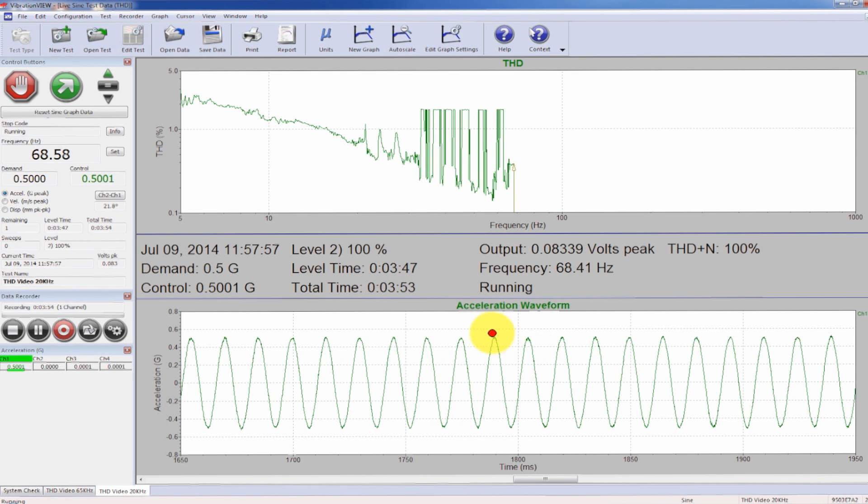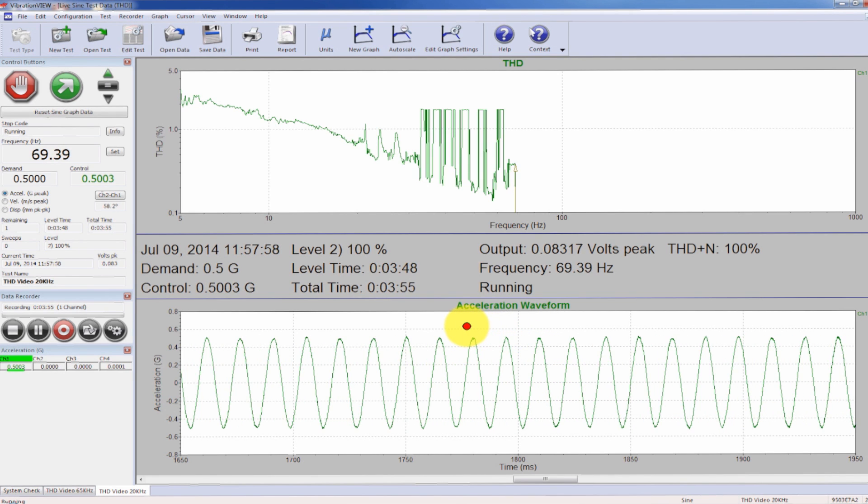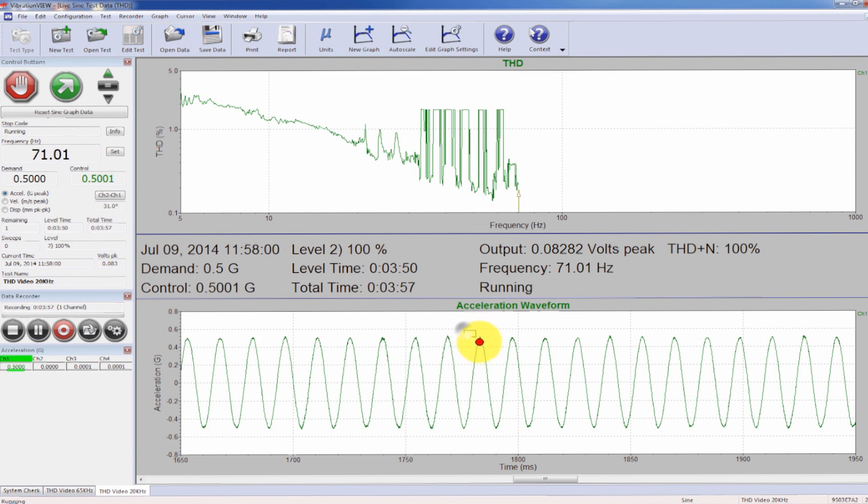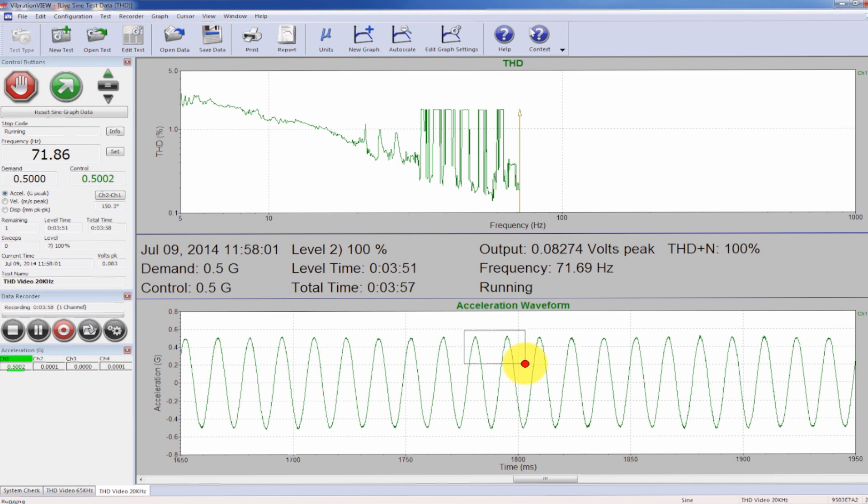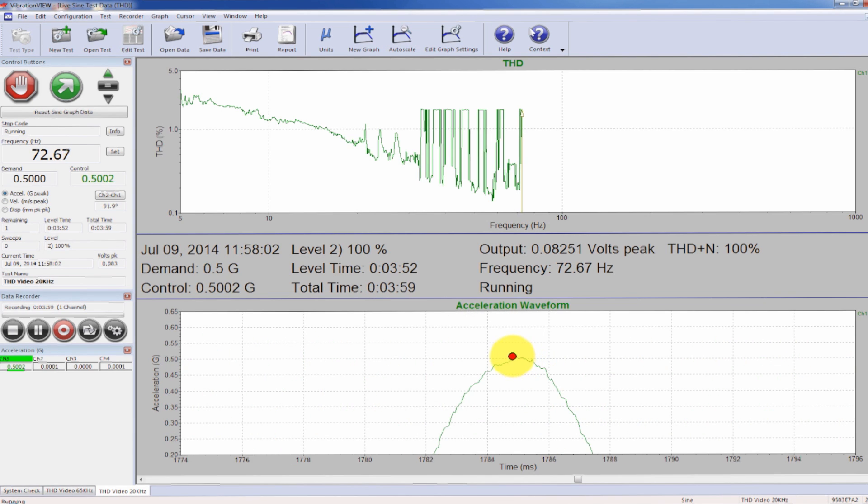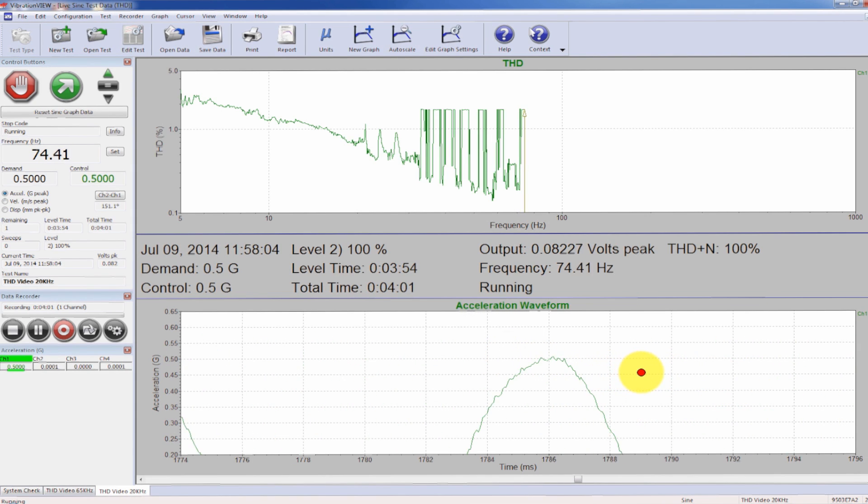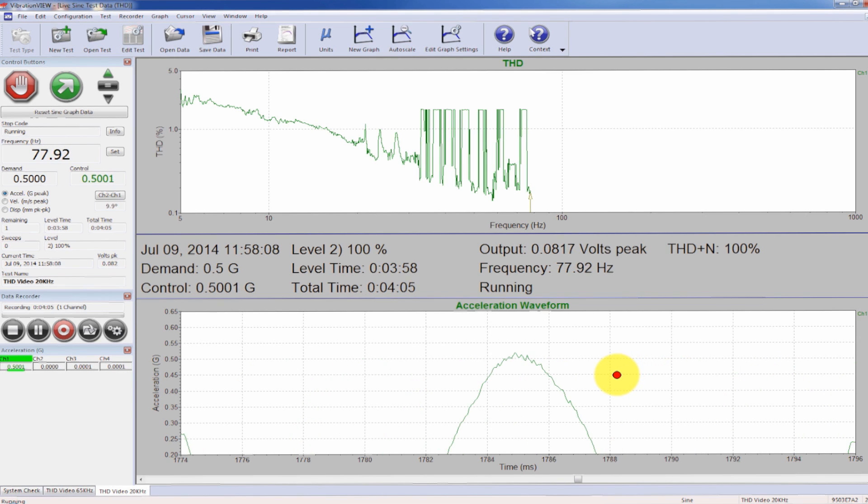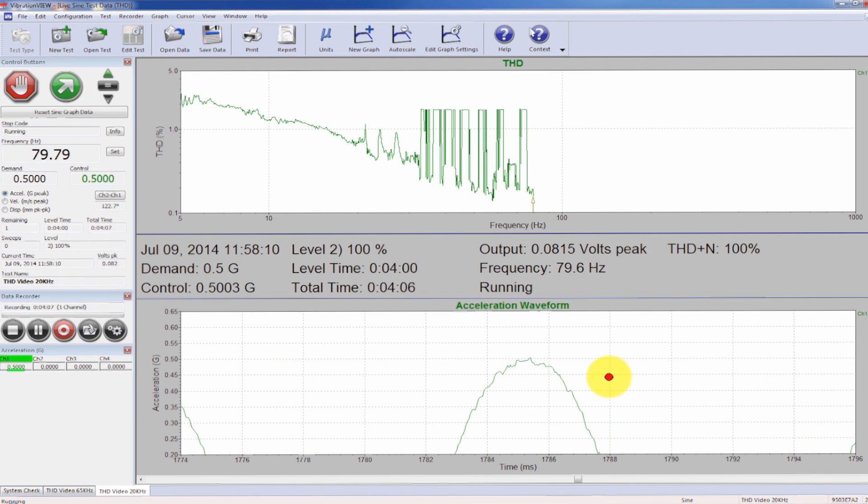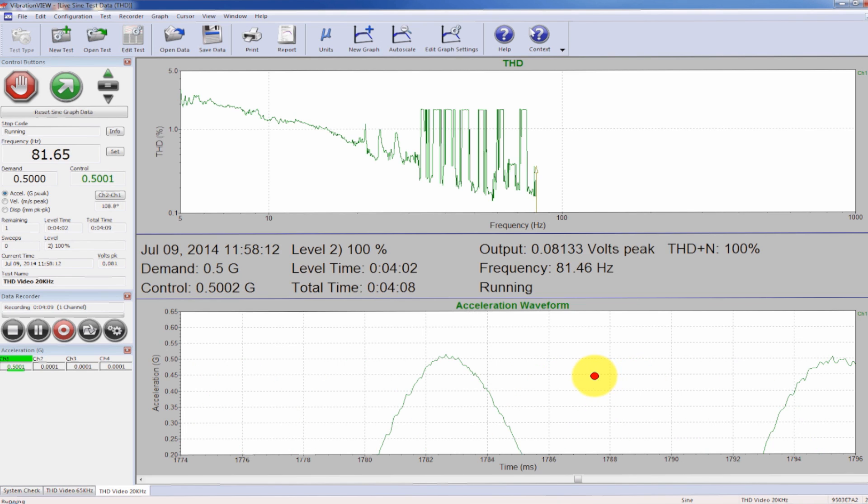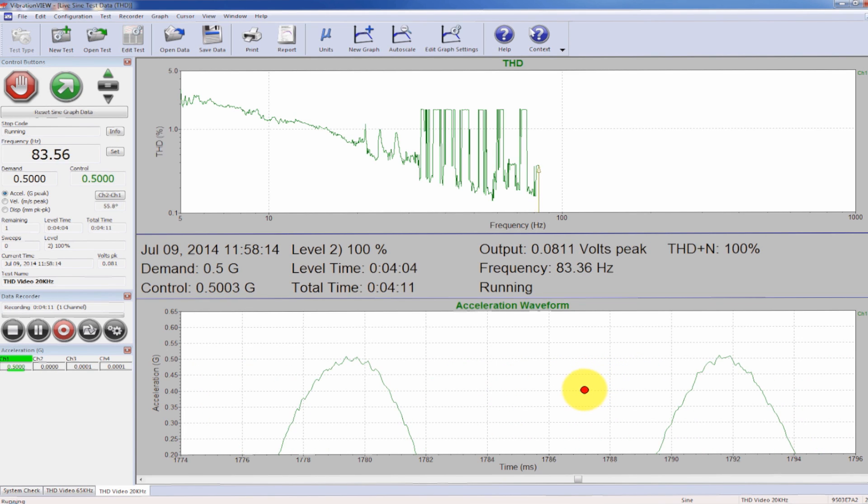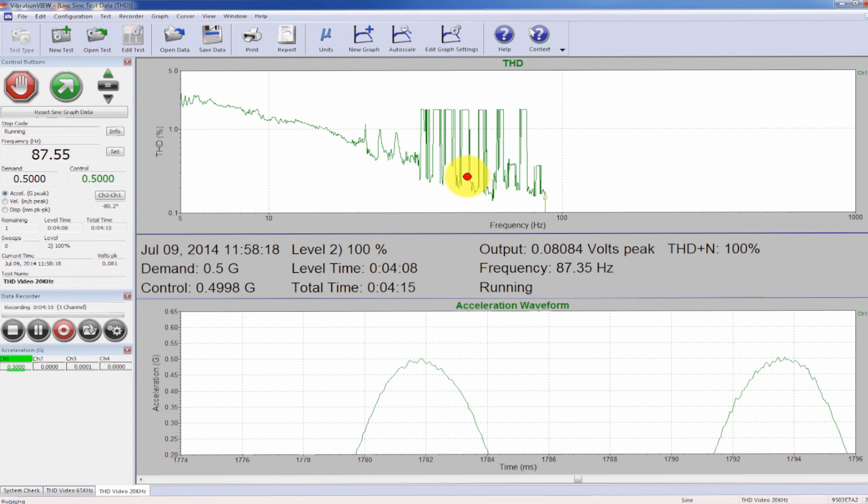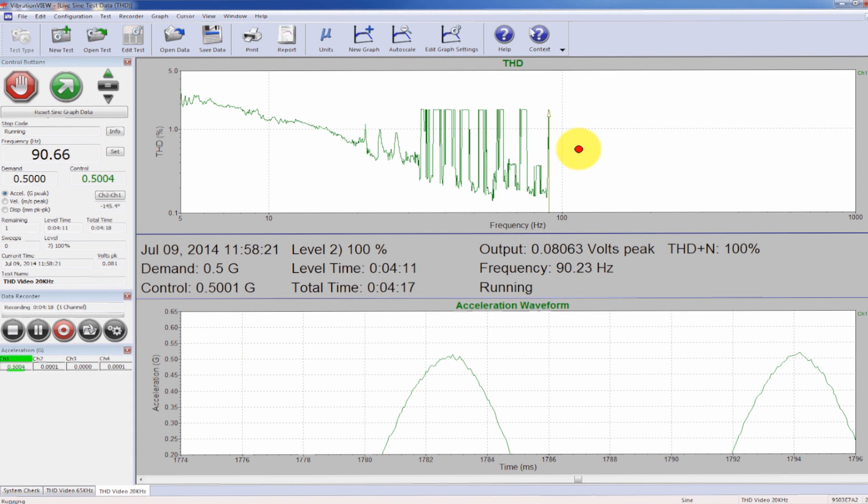You can look at the waveform already. And if I zoom way in at the peaks, you can see that this is actually the distortion that we're measuring. You can see in a perfect system, which would have a 0% distortion or total harmonic distortion, this would be a perfectly smooth sine wave. Since that's not the case, that's where we're getting that 1% approximately for this system.